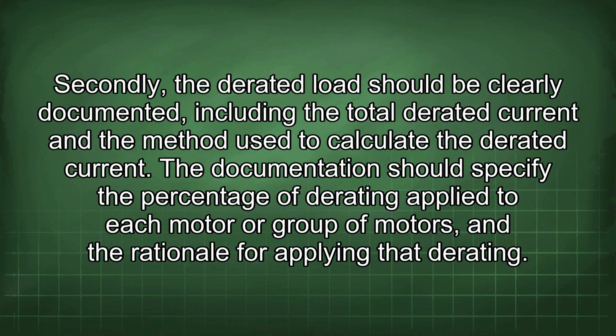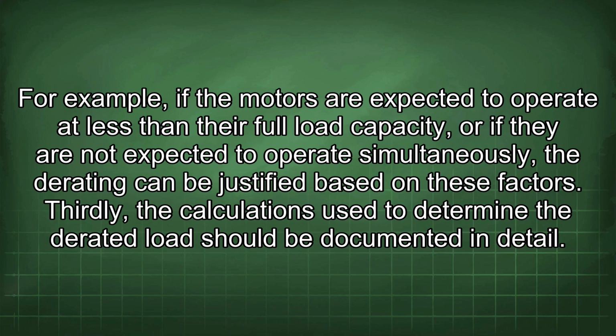Secondly, the derated load should be clearly documented, including the total derated current and the method used to calculate the derated current. The documentation should specify the percentage of derating applied to each motor or group of motors, and the rationale for applying that derating. For example, if the motors are expected to operate at less than their full load capacity, or if they are not expected to operate simultaneously, the derating can be justified based on these factors.